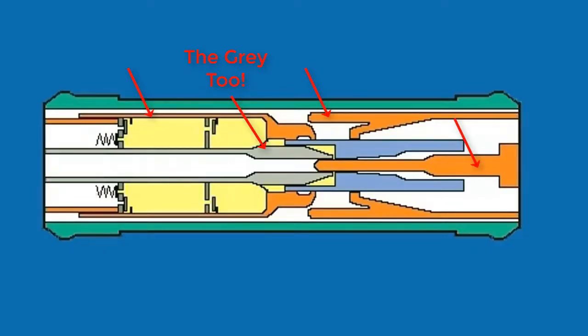The orange parts are the current carrying parts of the breaker. On the left is the moving contacts and on the right are the stationary contacts. Here we have the main current carrying contacts on the moving side, and here are the contacts on the stationary side. Inside these cylinders we have our breaking gas, or puffer volume as it may also be called, and in the middle of the breaker we have our arcing contacts. There are also refill and overpressure valves on the puffer cylinder, and a nozzle used in the breaking operation that will show up again later.